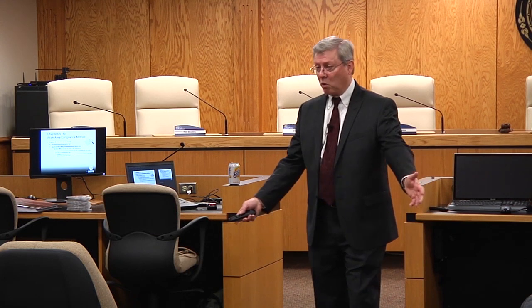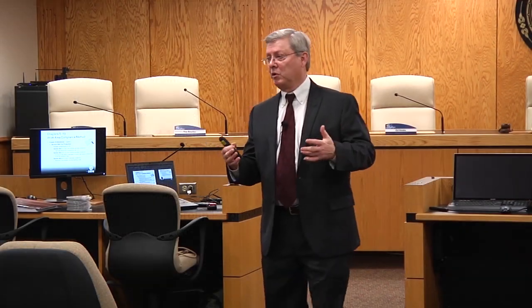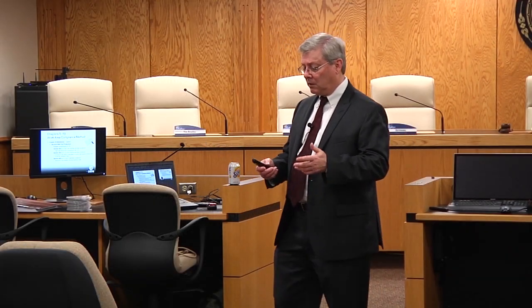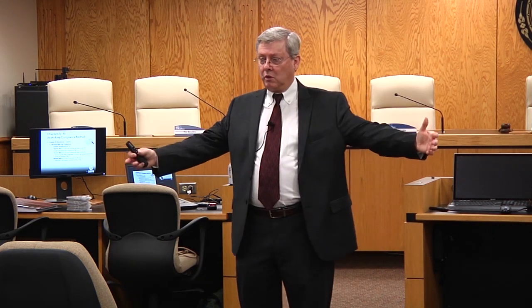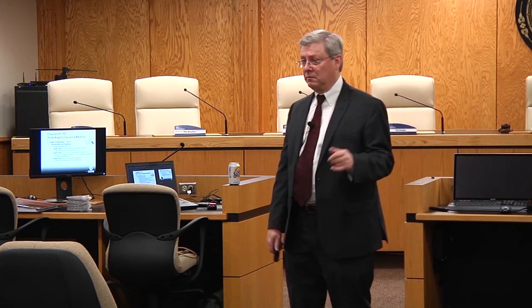There are places in the code that allow an open stair at the bottom, but you must have one-hour rating between that stair and the unit at the top. Sprinkler requirements under section 903 of the building code are usually triggered by how much area is affected by a potential fire without rated separation, or by the number of people in the space. Those two things — fire area and occupant load — drive sprinkler requirements.